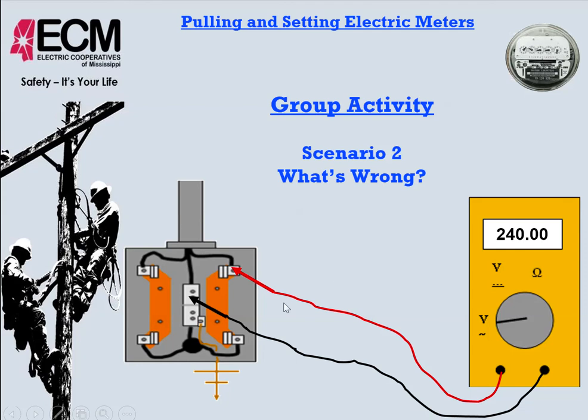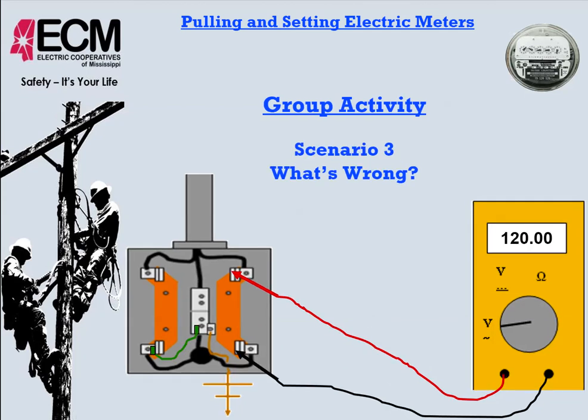Next scenario, scenario 2. We've checked from what we assume to be our neutral lug or our ground lug to our line side lug on the right side, and we get 240 volts. What would be the problem here? The problem would be that we have probably hooked our weather head up wrong, and our neutral is hot. If we check from over here, we're probably going to get 120 volts between these two, and we're only going to get 120 between these two as well. So we've probably made our neutral hot on this one if we get 240 volts from our neutral to our line side lug.